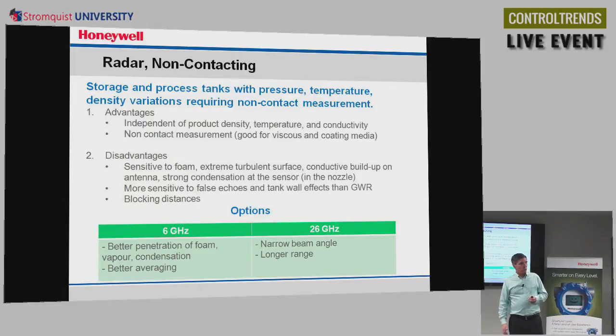Now the advantage, one of the big advantages, is that it's non-contacting. We don't have to worry about a waveguide coming in contact with impellers or agitators. It is not going to come in contact with corrosive environments necessarily. And it's independent of the product density, so it's going to bounce off the surface no matter what the density is, as long as there's a change in dielectric.